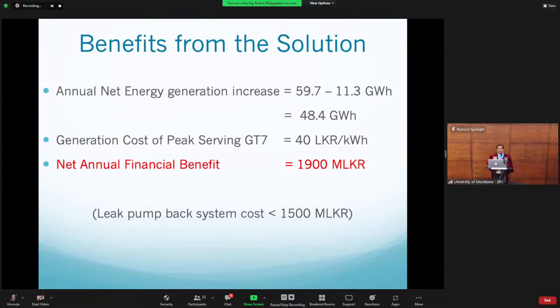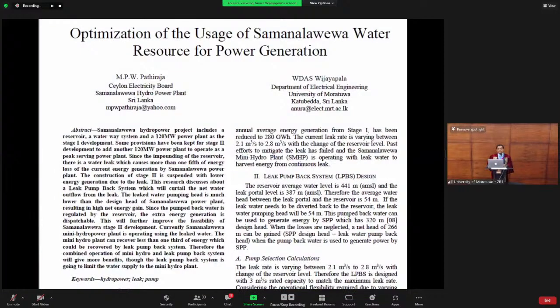Now this is dispatchable energy, that is, in the reservoir water. So we can dispatch it in the evening when the electricity generation is most costly. For example, GT7, which is serving the peak in the evening at Kelanitissa, costs about 40 rupees per kilowatt hour. So at this rate, if you calculate the value of this water, it translates to about 1.9 billion rupees every year. And then we designed the leak pump back system and found the cost to be less than 1.5 billion rupees. So it is less than 1 year's payback period. And so every year for a very long time to come, 1.9 billion rupees, so nearly 2 billion rupees in today's energy terms, will be available to CEB and to the nation. And we made a publication on this in, I think, Mercon 2016.